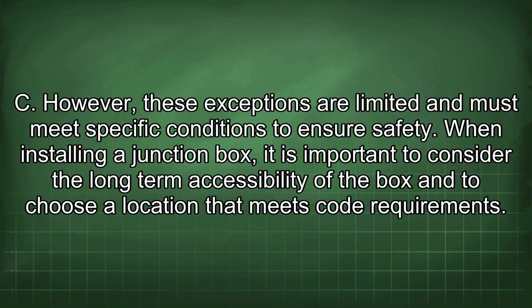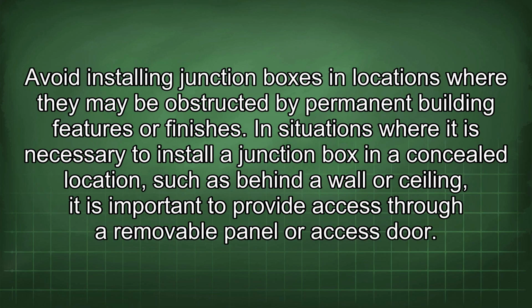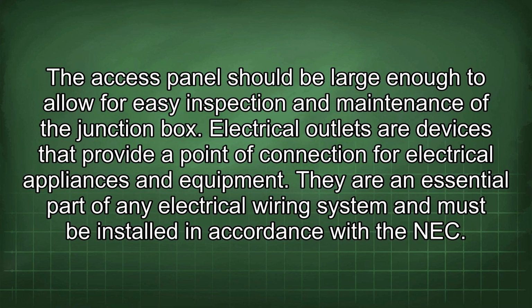When installing a junction box, it is important to consider the long-term accessibility of the box and to choose a location that meets code requirements. Avoid installing junction boxes in locations where they may be obstructed by permanent building features or finishes. In situations where it is necessary to install a junction box in a concealed location, such as behind a wall or ceiling, it is important to provide access through a removable panel or access door. The access panel should be large enough to allow for easy inspection and maintenance of the junction box.